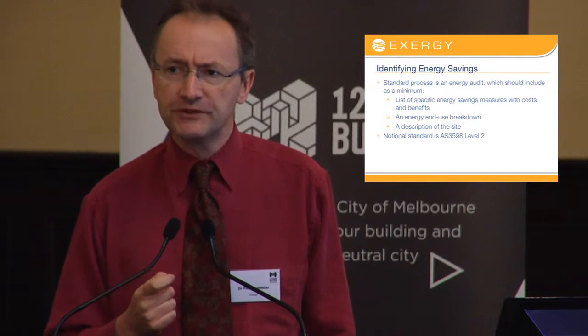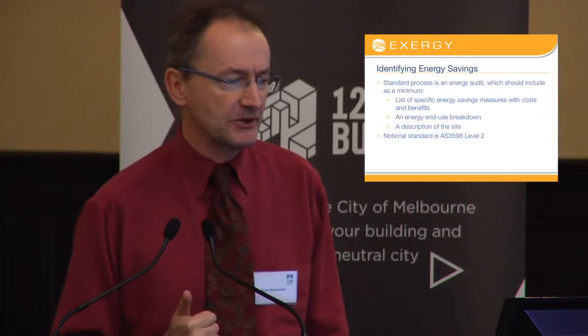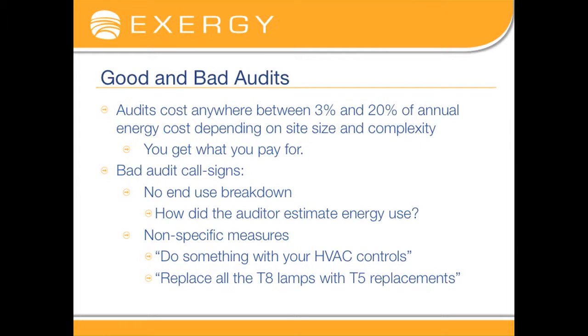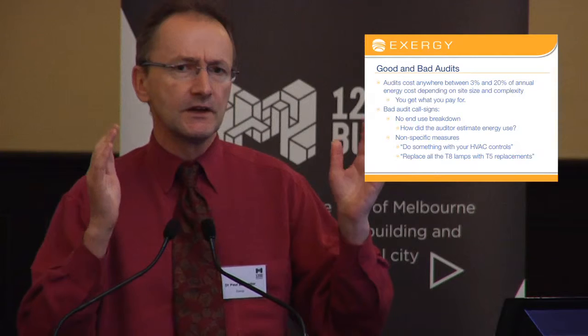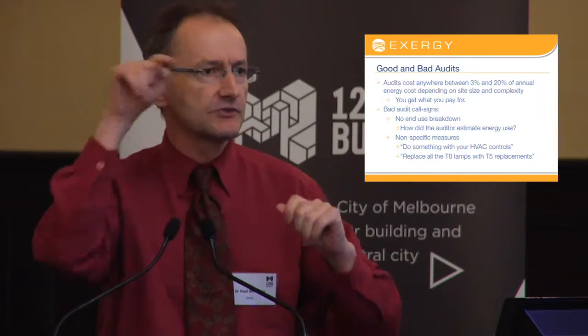From a process point of view, what you want, as a minimum, is a list of specific energy savings measures with costs and benefits, an energy use breakdown, and a description of the site. As for the call signs of a bad audit: the first is that the auditor hasn't attempted to create a breakdown of energy consumption — something even as simple as a pie chart showing how much goes to the fans, how much to the chillers, how much to the lighting.